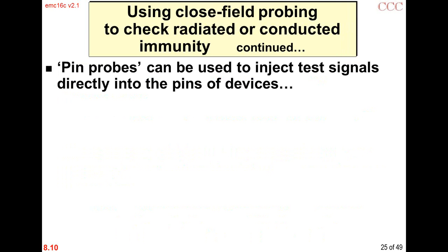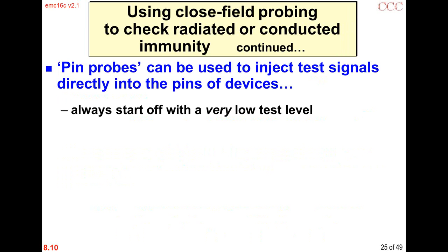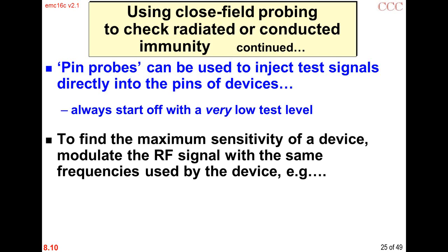We can use pin probes to inject test signals directly into the pins of devices. It's important to always start off with a very low test level and then gradually turn it up, because we don't want to destroy the device at all.